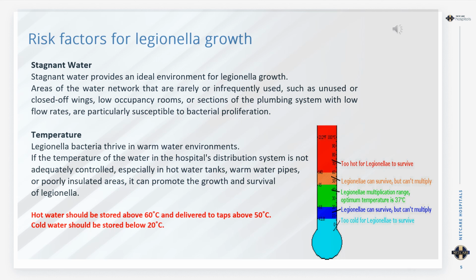If you look at the thermometer in the picture on the right, it really breaks it down in terms of Legionella growth, where we see anything above 60, it's too hot for Legionella to survive. The orange square shows us Legionella can survive, but it cannot multiply, and this is between 50 to 60 degrees. Our green square shows us the Legionella multiplication range, where the optimum temperature is 37 degrees.